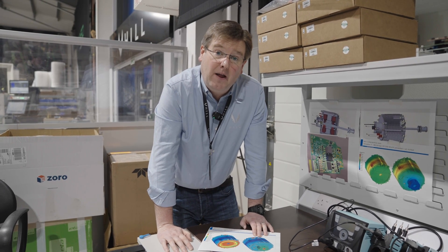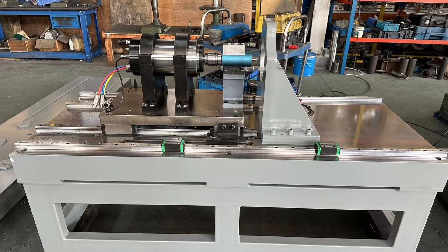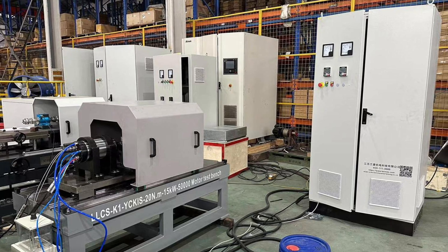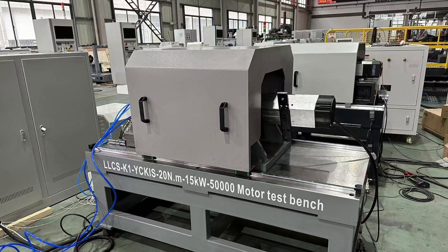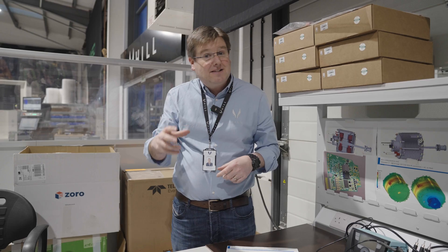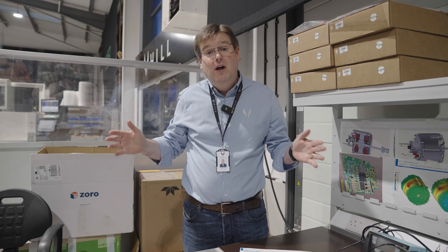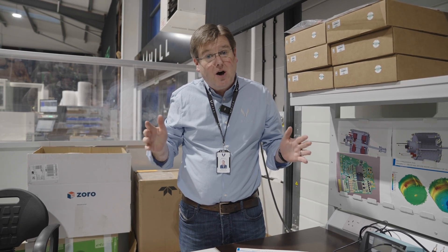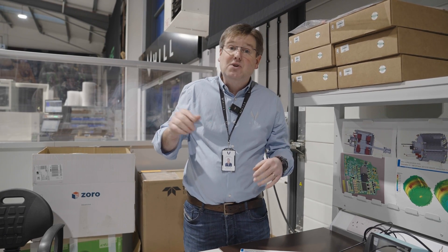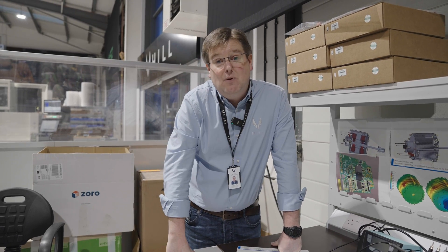GenU has just been out to our suppliers to do the factory acceptance test on the test rig for testing all of the starter generators, both in development and then in production. This is a unit that can drive the generator part of the starter generator as a generator, and then act as a load as the starter motor works throughout the full operating range, all the way up to around 50,000 RPM. It will be arriving here in the UK towards the end of April, directly to PC1, ready for installation.